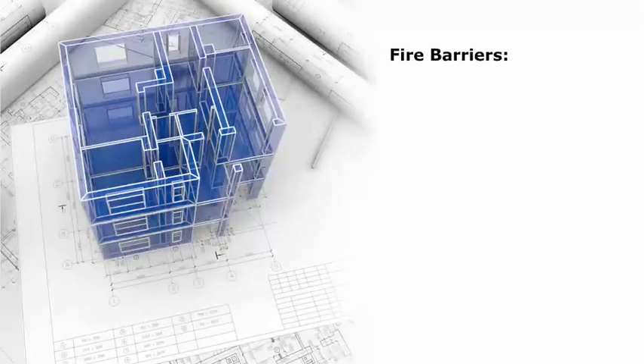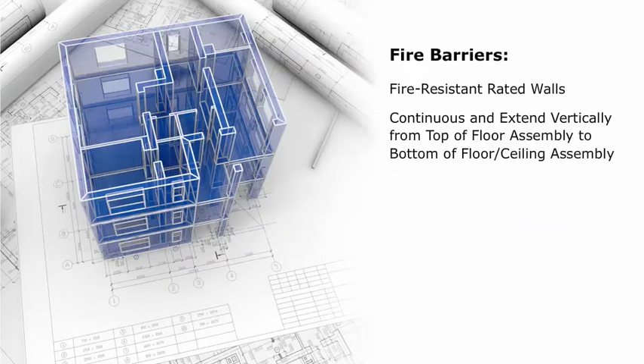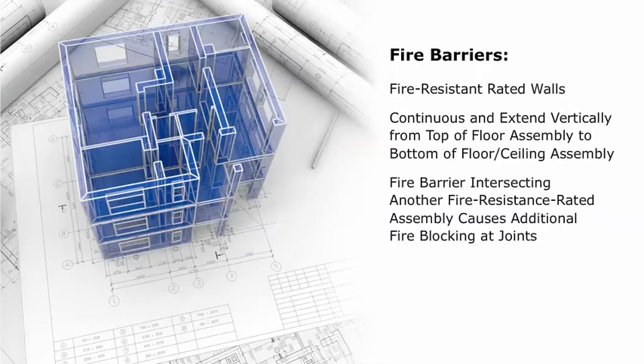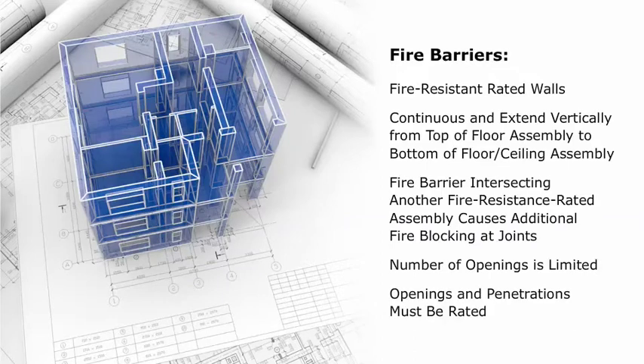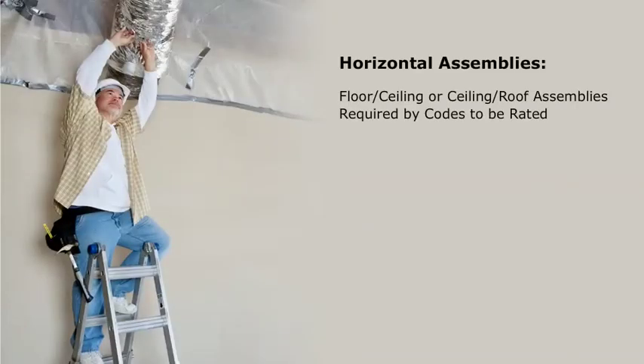Fire barriers are walls with a fire resistant rating that in most cases must be continuous, extending vertically from the top of a floor assembly to the bottom of a floor or ceiling assembly. For example, a fire barrier would extend through a suspended ceiling to the slab above. When a fire barrier intersects another fire resistance rated assembly, additional fire blocking is required at the joint. The number of openings, including doors and windows, is also limited and must be rated.